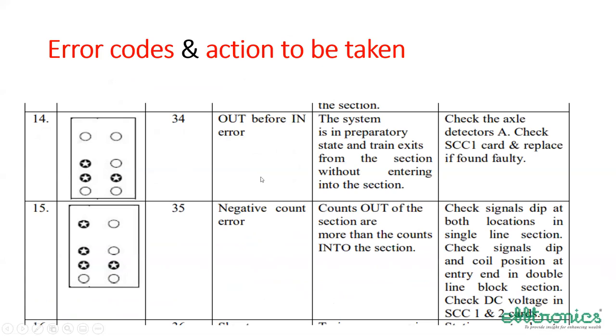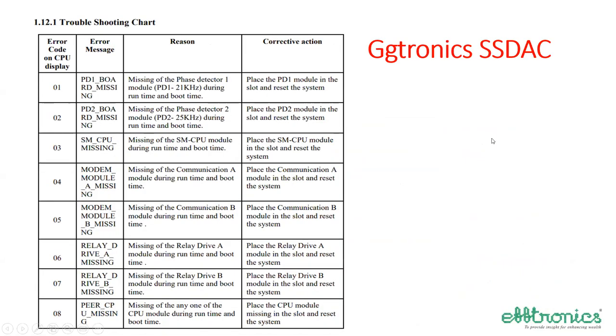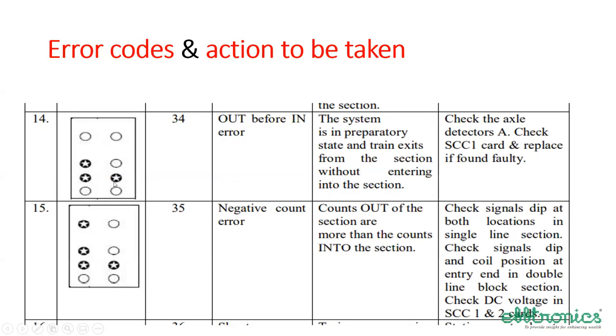Based on that, it is given in the manual. Like, 34 error means this, where 3 are lit. 35 means, as we have just seen, these 4 red LEDs are lit. These LEDs are in the CPU card. So it gives the reason, then it gives what action is to be taken by the maintenance person. Similarly, Ggtronics SSDAC also provides a similar thing, what is to be done. But here, I think, for error codes they directly display the number. This is for CEL.